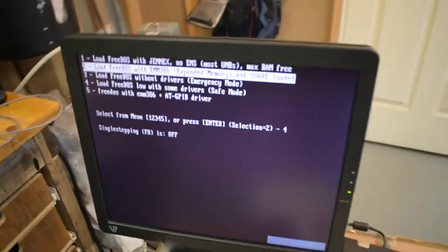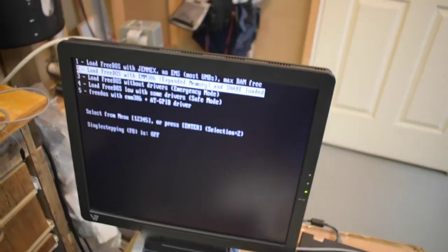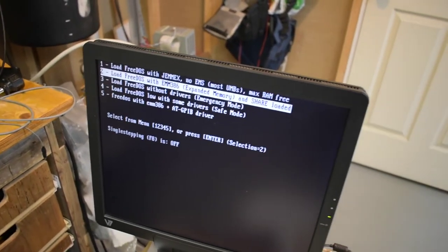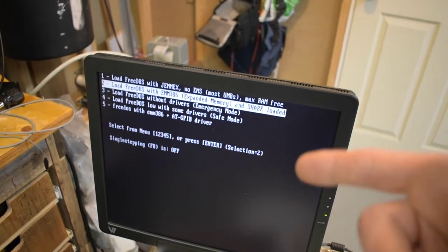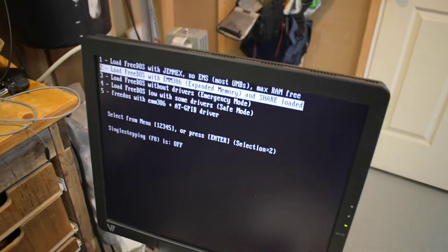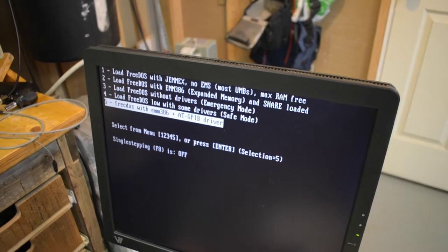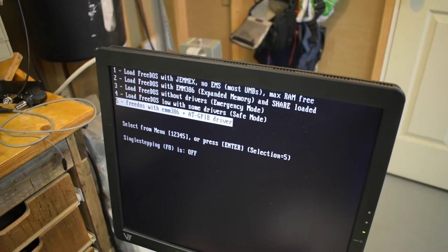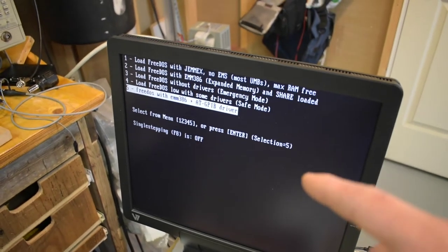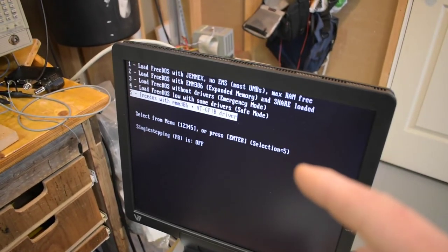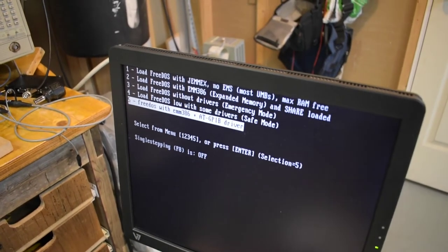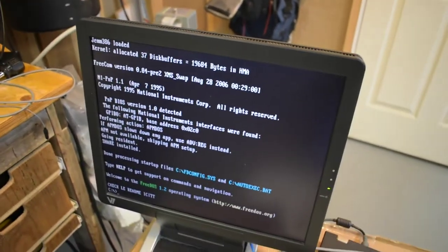Oh yeah, it's just booting up here. And let me see. Oh yeah, I'm running FreeDOS actually, and FreeDOS is really, really very nice. So it lets you do these configuration options. These are all part of the autoexec.bat, so I added one option at the last here to load the National Instruments GPIB drivers. You only want those if you're dumping the calibration data or the firmware. If you want to run the adjustment software, I think it won't work, so you need to just boot into straight DOS. I'm using this one here. Alright, I'll come back to that later.